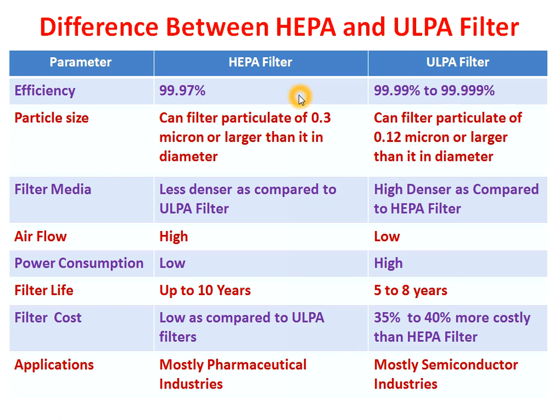Now we will see particle size. The HEPA filter can filter particulates of 0.3 micron or larger in diameter, whereas the ULPA filter can filter particulates of 0.12 micron or larger. That means the ULPA filter can filter smaller particles than the HEPA filter.